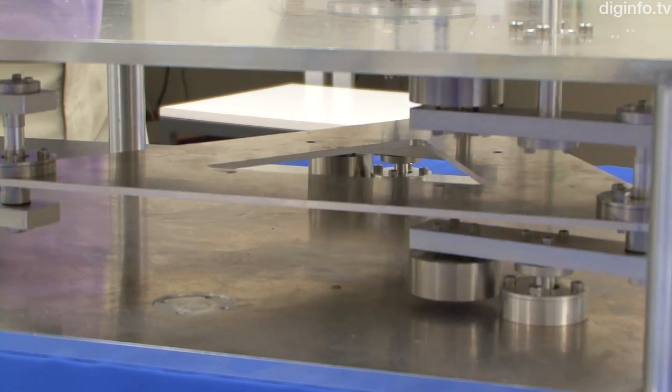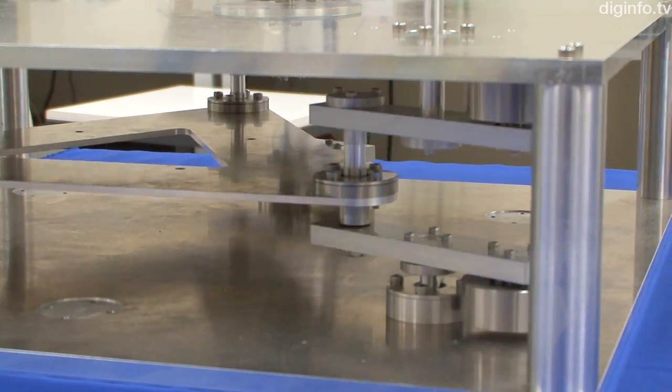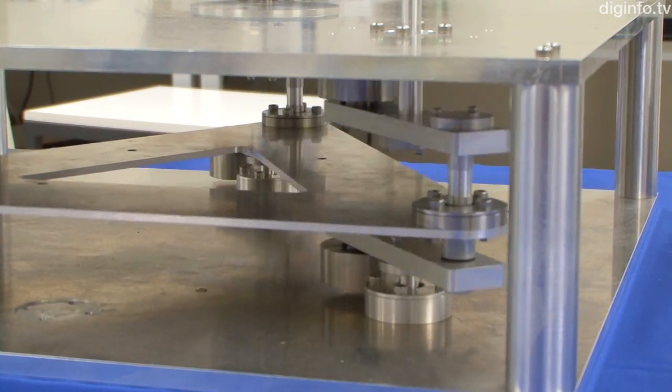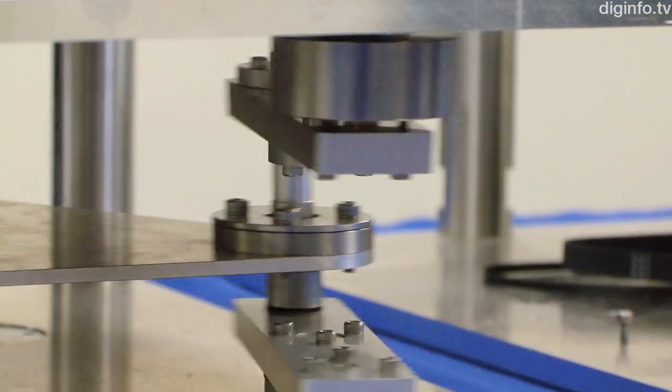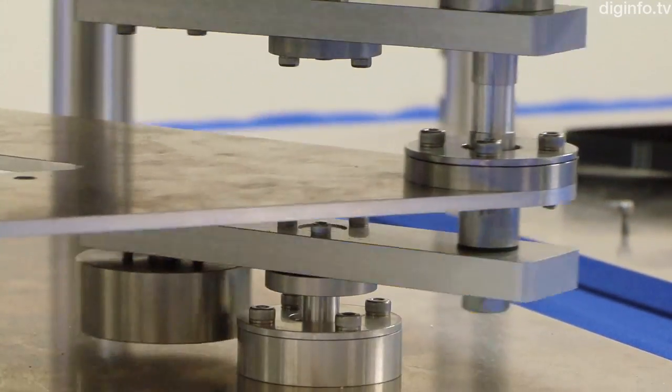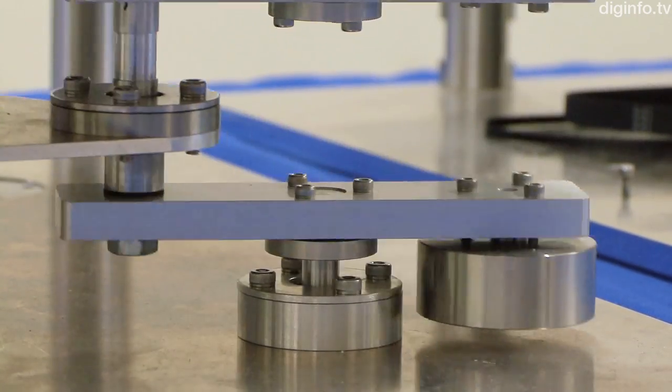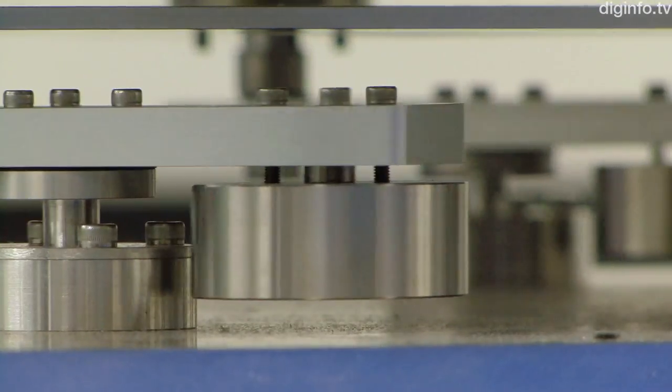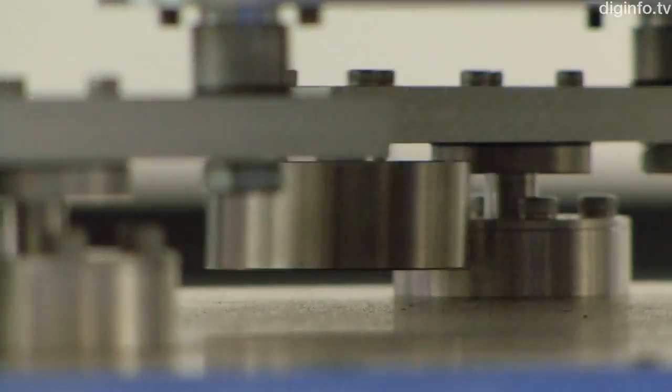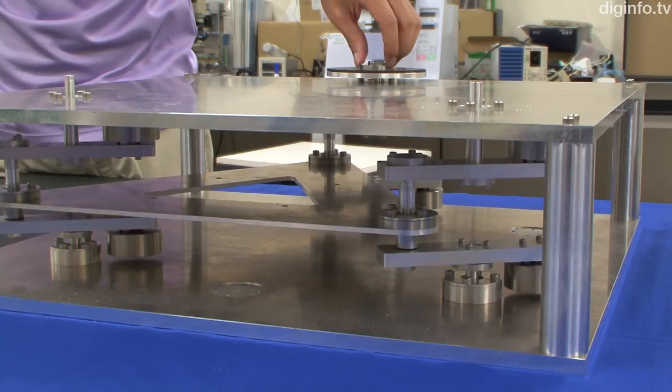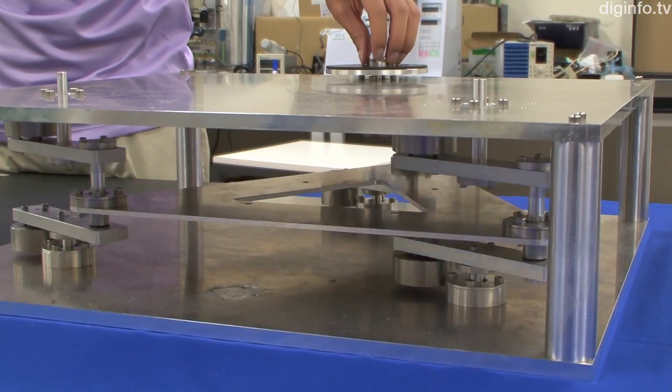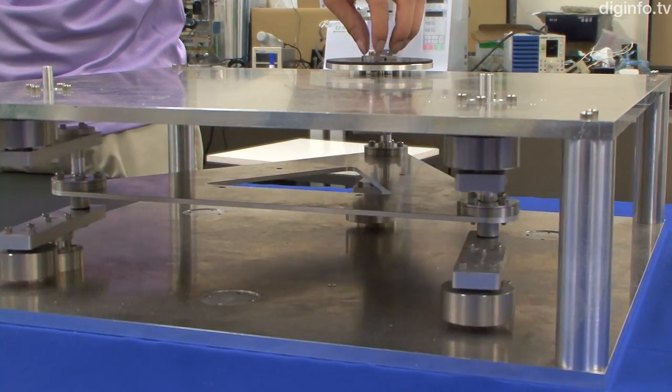A research group led by Professor Norio Inou and assistant professor Hitoshi Kimura at the Tokyo Institute of Technology has developed technology for testing a three-axis accelerometer. It can measure not only the sensitivity of each axis but also the direction vector of each sensor to an accuracy of one thousandth of a degree. This technology works by generating a uniform circular motion which imposes sine wave acceleration on three sensors simultaneously.